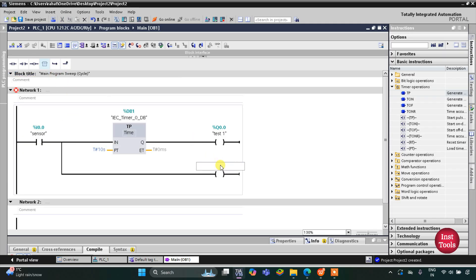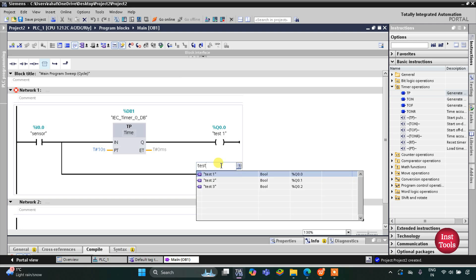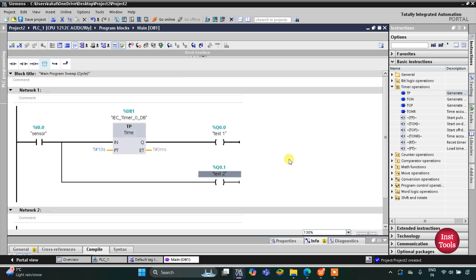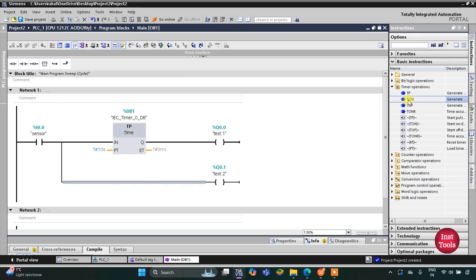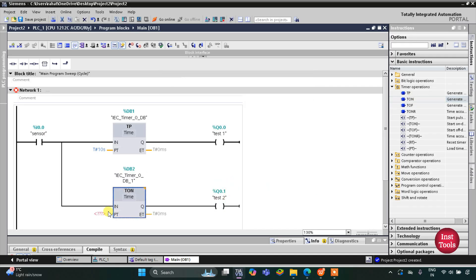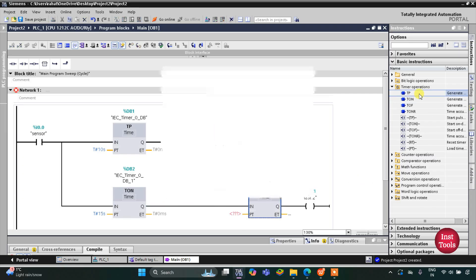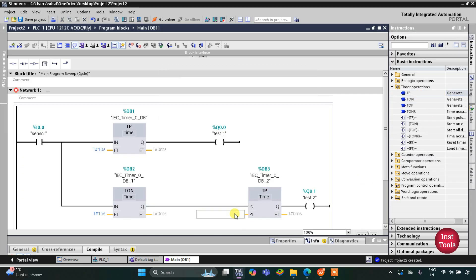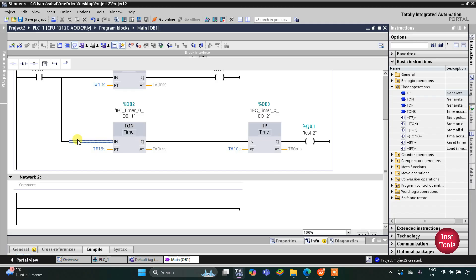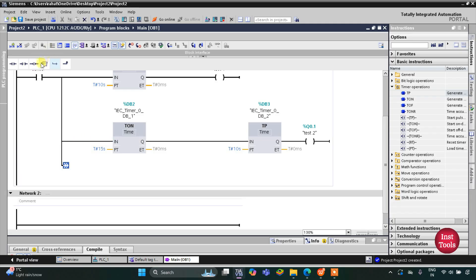The coil will represent Test 2. Test 2 will occur after Test 1 with a delay of 5 seconds, giving a total time delay of 15 seconds. So the preset value for the TON timer will be 15 seconds. Test 2 will also run for 10 seconds, so the preset value for the TP timer for Test 2 will be 10 seconds. Then I will open the branch and add another coil.